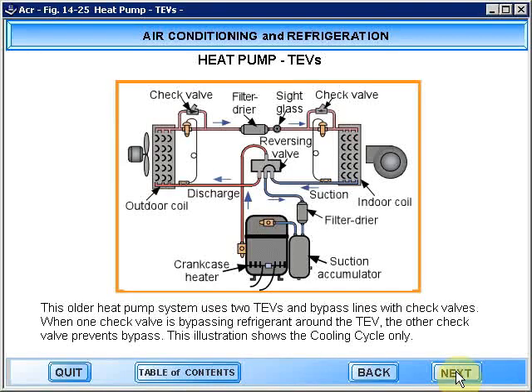This older heat pump system uses two thermostatic expansion valves and bypass lines with check valves. When one check valve is bypassing refrigerant around the thermostatic expansion valve, the other check valve prevents bypass. This illustration shows the cooling cycle only.